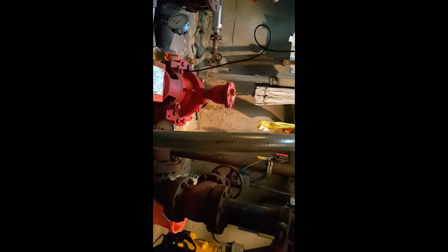If you see water running like this, it is perfectly normal. You want that to keep the packing lubricated. If it starts spraying water or it's getting out of control, then I'll adjust it to have the same drip as the other side. And if you notice it starts getting hot while you're running, then you could open it up just a little bit more.